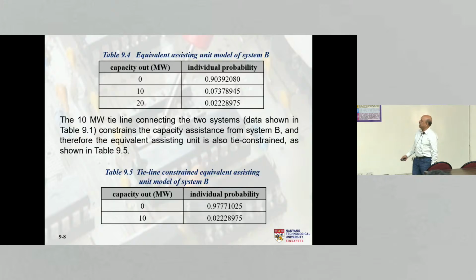So what do I do? Equivalent assisting model of unit B. So capacity out 0, I can get 0.9 times. Capacity outage 10, I can get 0.073 probability. And capacity outage 20, the probability is very, very low that it will supply me with any support. So the 10 megawatt tie line connecting the two systems constrains the capacity assistance from system B. I can only transfer 10 megawatt, not 20 megawatt.